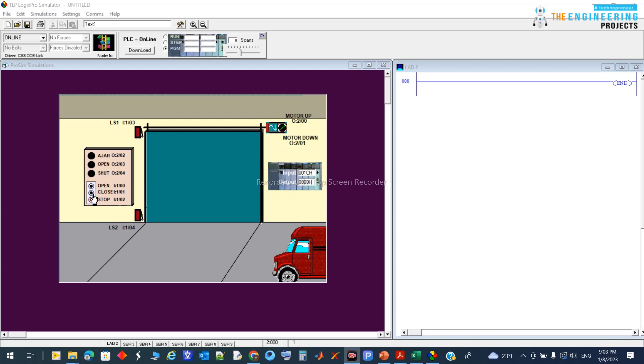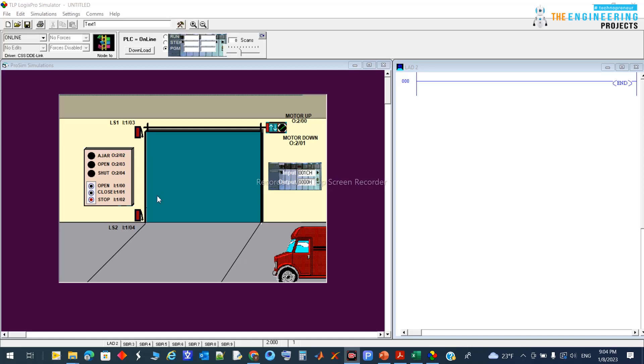We have an open request and a close request — one switch for open, one switch for close, and a stop at any time if there's a problem. We also have limit switches at the top and bottom. These limit switches detect the start and end position of the door to protect the motor, because if the motor continues opening past the end, the load overloads the motor and it will blow up. The same applies when closing.